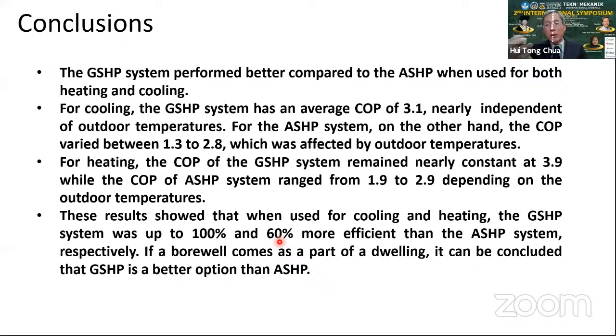You've seen the drilling that took 14 days and the installation of the heat pump, but the heat pump itself, the capex of which is actually quite similar to the air source heat pump. So one of the major findings that we have arrived at is that if this were to double up with the borehole irrigation, which is quite commonly done in Perth, I'm not sure about Indonesia, that means we extract the groundwater for irrigating the lawn and the garden. Quite commonly done here. Then we find that this scheme can rapidly pay back itself by no more than 4 years, and actually sometimes as fast as half a year, because of the efficiency gain.